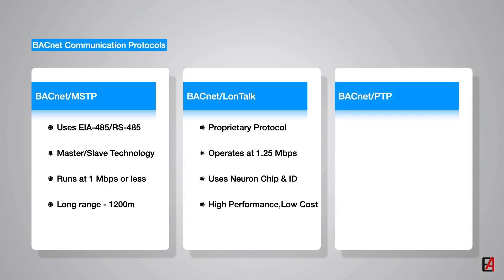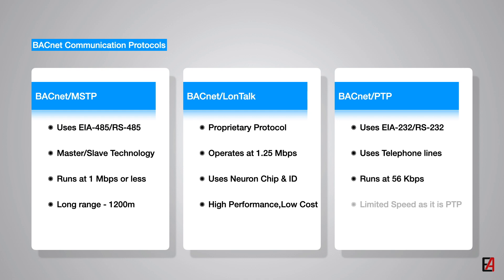The final data link and the physical layer option in BACnet is the point-to-point protocol. The PTP protocol accesses the communication medium through RS-232 interface. A typical application would be to connect a telephone modem for dial-up access to a remote building automation system. BACnet PTP runs at a very low speed of 56 kilobits per second as it is only a point-to-point communication.